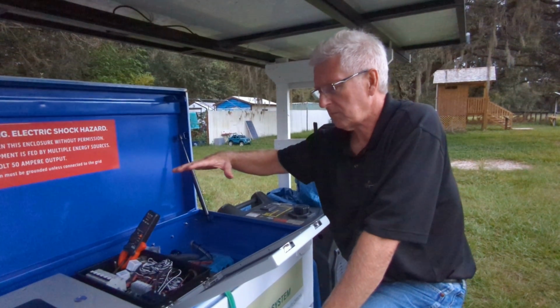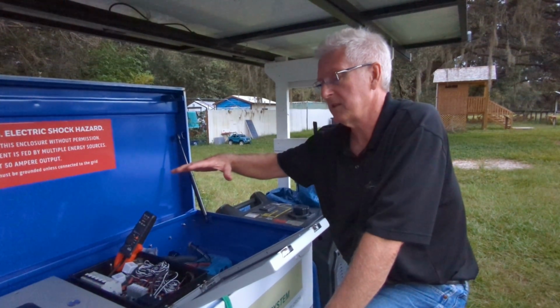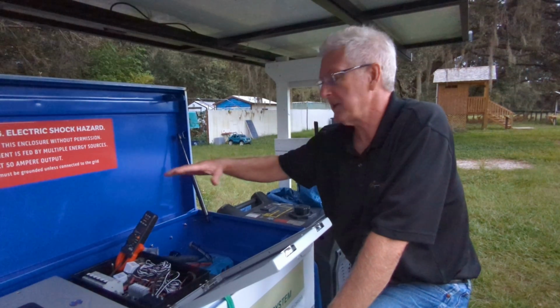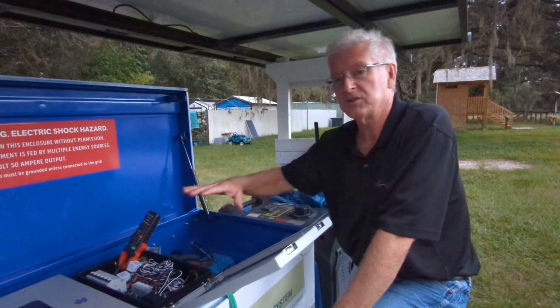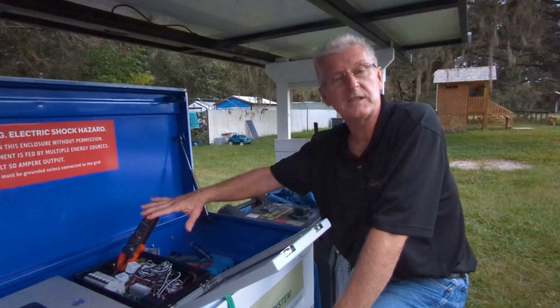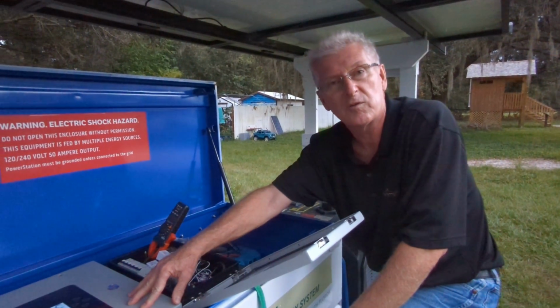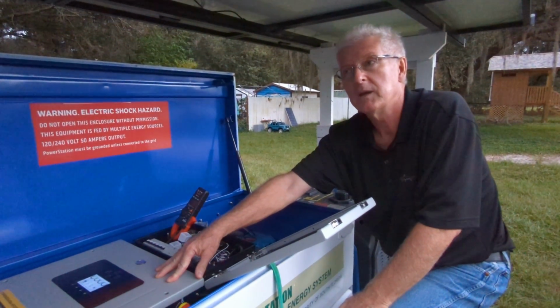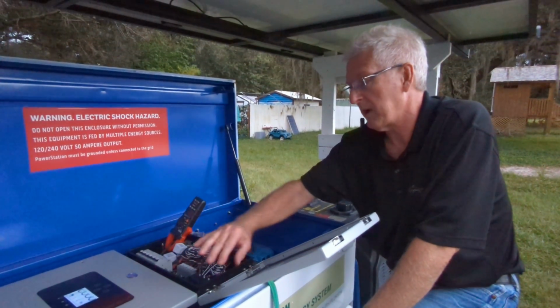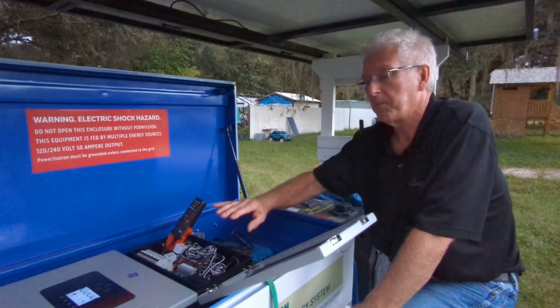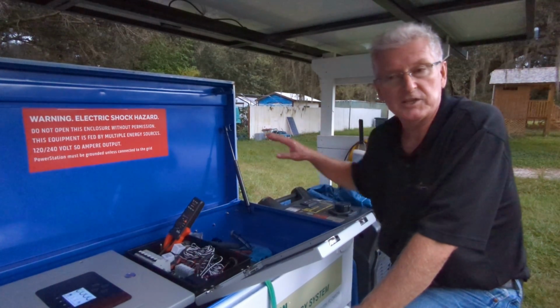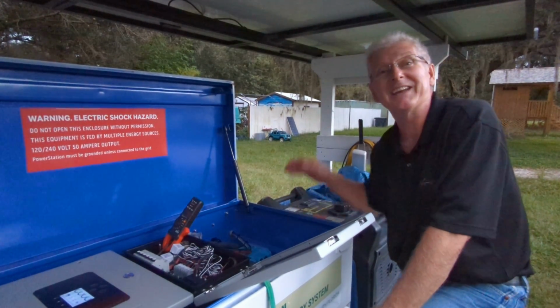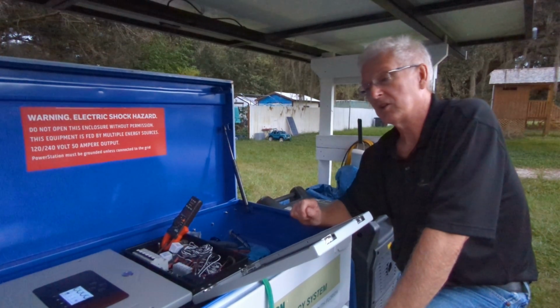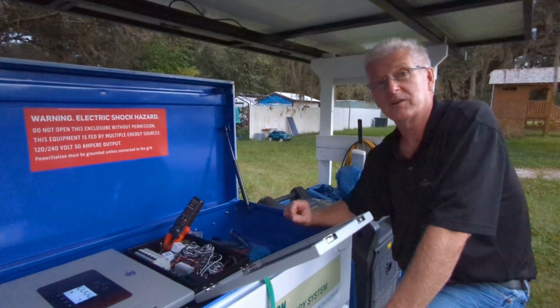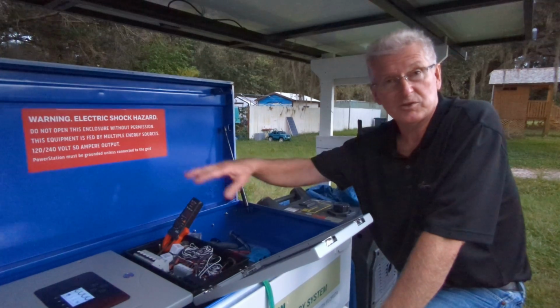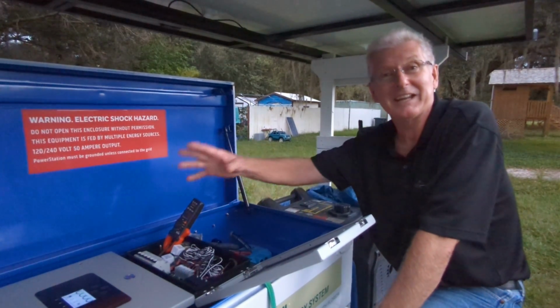So what we want to do instead is manage the black leg, manage the red leg, so the sum total of those don't exceed the 5 kilowatt capacity of your inverter. We have a better chance of doing that now. Not worry anymore about the grid breaker tripping. Not worrying anymore about the generator starting, because you know you have to have the key in it and turned on. Right. And you can always test that by doing a forced start. Yeah. And you don't know if our parameters are wrong for the generator because we never had the key in it and turned on. That's right.